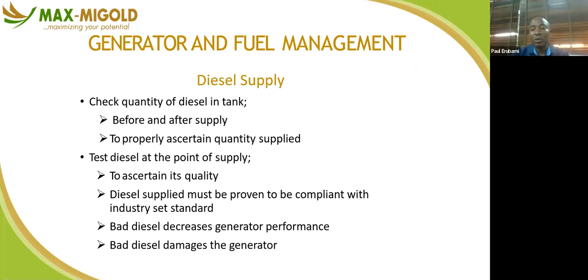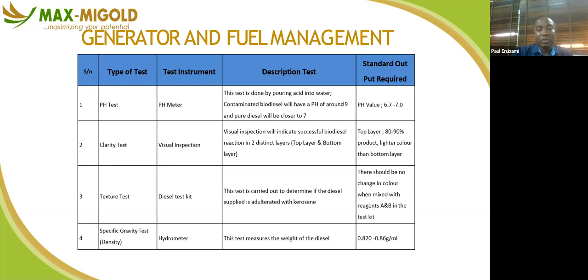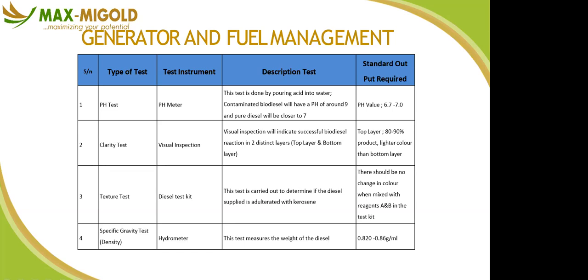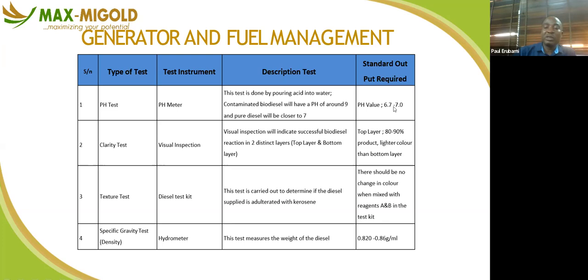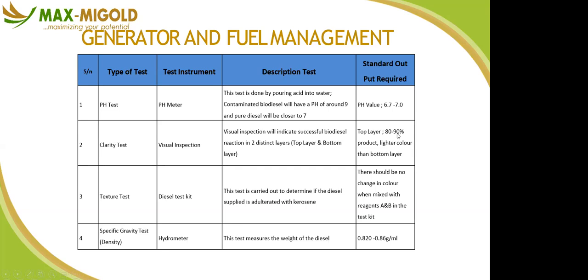Before you accept diesel, these are the things you ascertain. You check the quality. Diesel supply must be proven to be compliant with industry set standards. We have values and testing kits that we use to determine whether the diesel is fine or not. We have the density test, the clarity test, the texture test, so you check whether there is water or not, and so on. Before you take the diesel, ensure that all these tests are carried out. So, the pH test: good diesel will give you a value of 6.7 to 7.0.